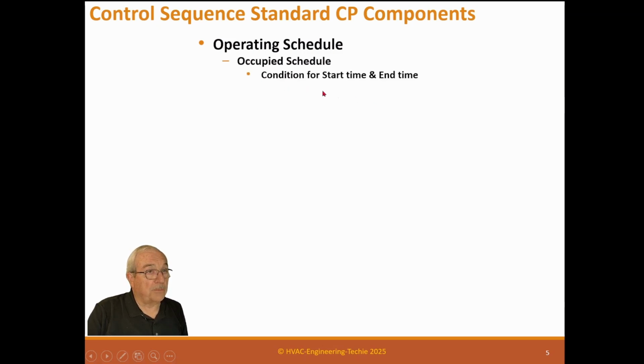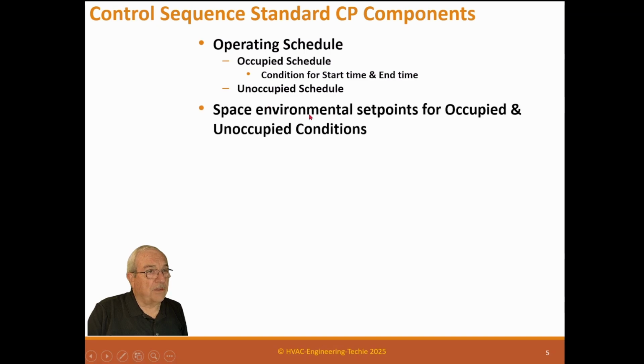We know when the building's occupied. We know when it's unoccupied. We know what a start time and end time is, same for unoccupied. Space environmental set points for occupied and unoccupied conditions. Room set point dead bands, 1 to 3 degrees.